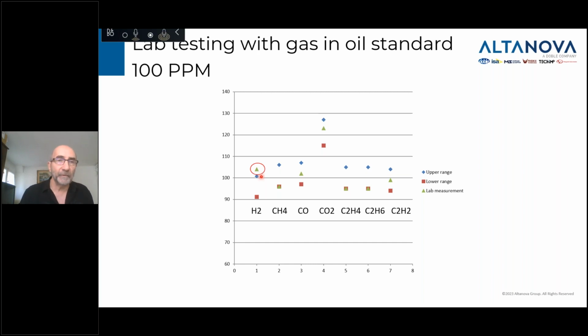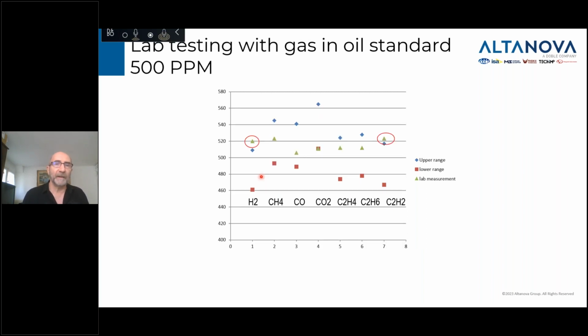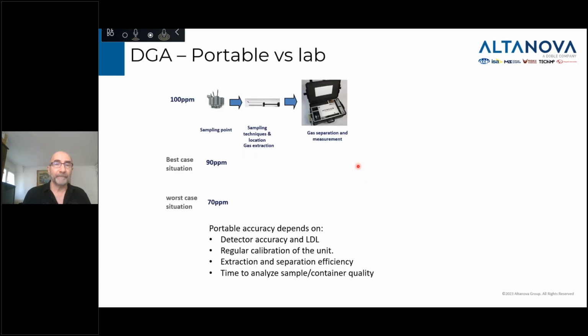On the same GC, we use a much higher level of gas at 500 ppm. Again, for the hydrogen they're measuring slightly higher, but the other gases are mostly in spec. On the acetylene, also, they're slightly higher. So except for those two points, in general that whole lab GC system, extraction and measuring, seemed to be pretty in line and pre-calibrated. That gives you the confidence that when you send an oil sample, the DGA result you get has a high probability of being pretty accurate.